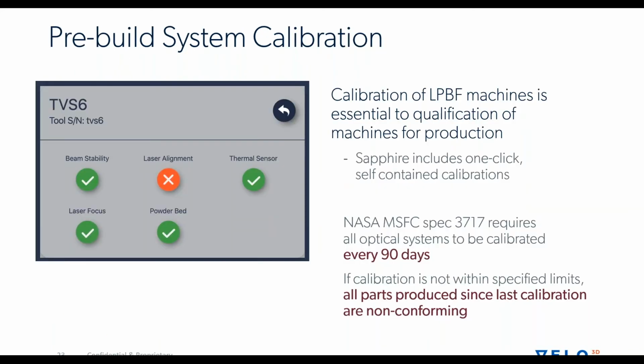The first aspect of this is machine health. And this is something that seems very rudimentary, but it really is something that's not addressed in a lot of the systems that have been available in the past. And I think, again, to go back to the NASA Marshall Space Flight specs, they're requiring the optical system of these machines to be calibrated every 90 days. And in the spec, when you read it, they basically give a rationale that says, we would like this to be done more frequently, but recognize that there's a lot of overhead and a lot of cost in doing this. So if we can do it every 90 days, that will at least suffice to give us confidence in the parts.